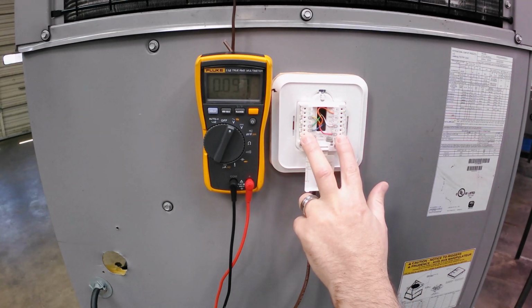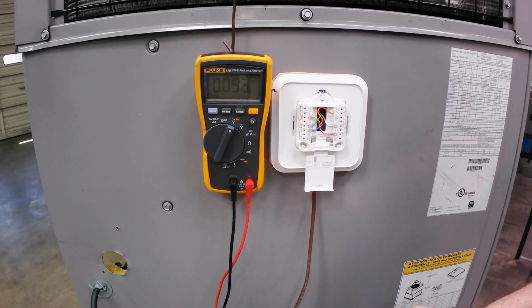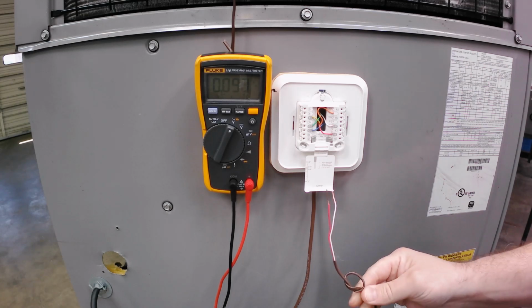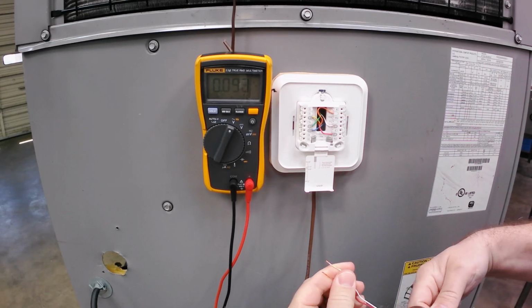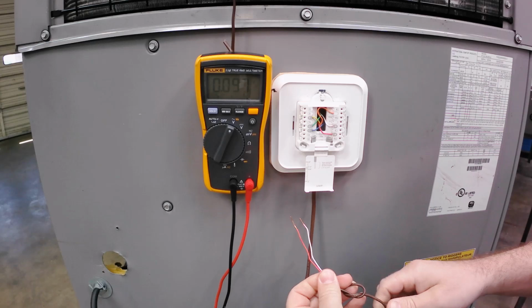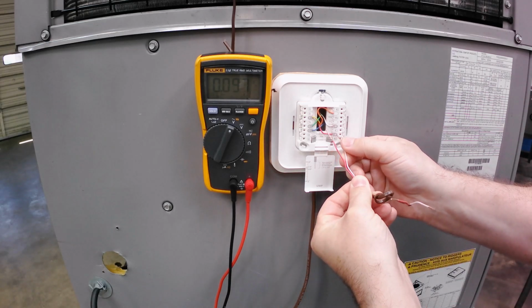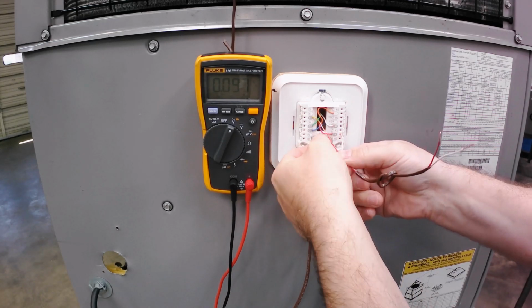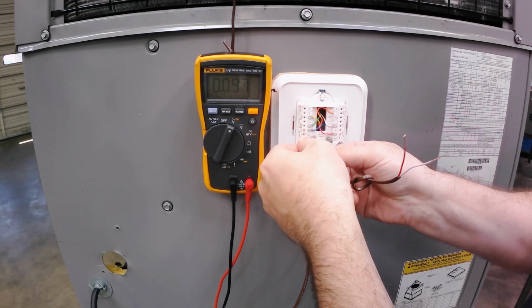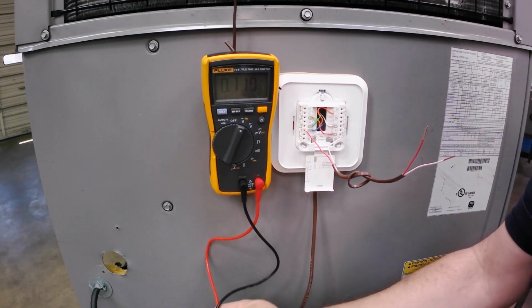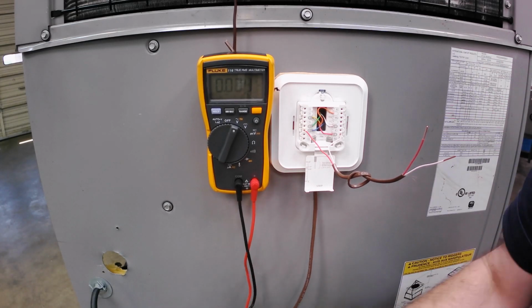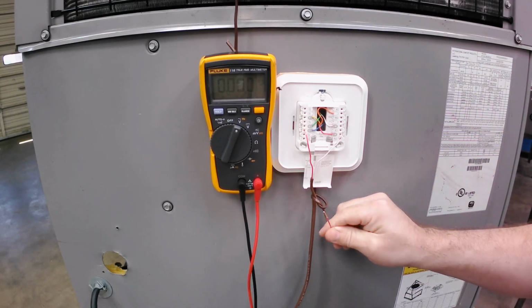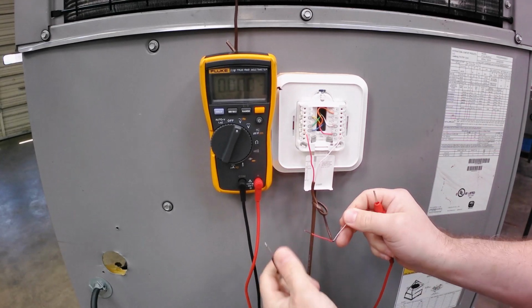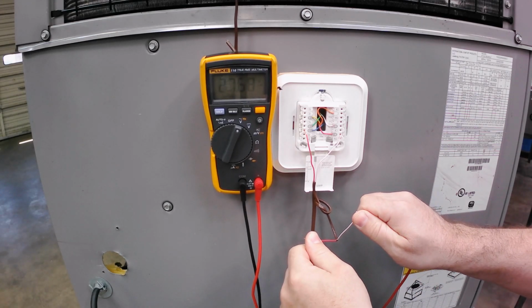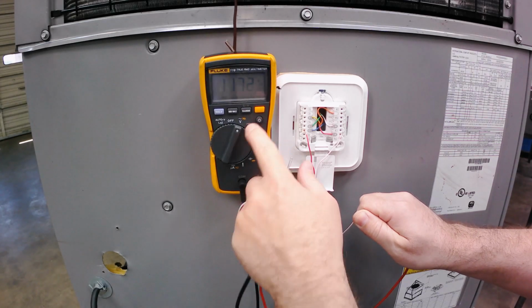If you have a thermostat subbase where you can actually see the pins, don't try to jam your lead in there. I've got a 2-wire piece of thermostat wiring, and I'll cut a length of scrap and put that in like my R and C, and then I have a little piece out here I can grab, and I can check 24 volts. You can see there, I've got 27 volts.